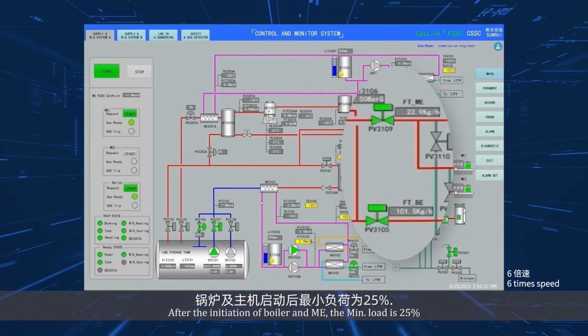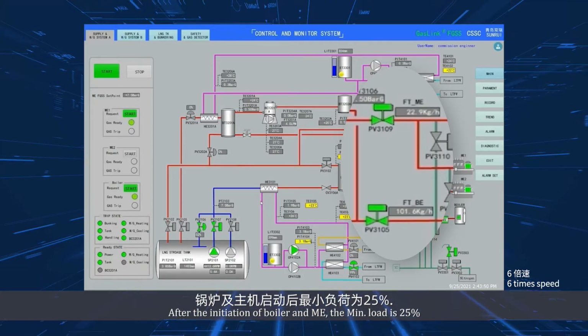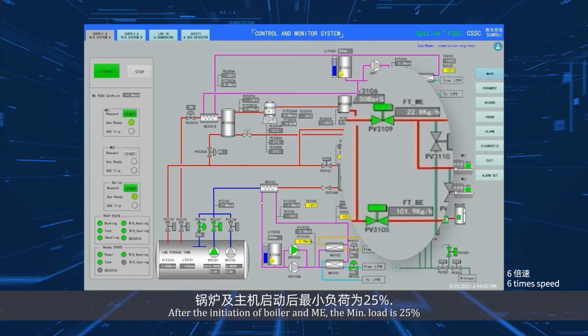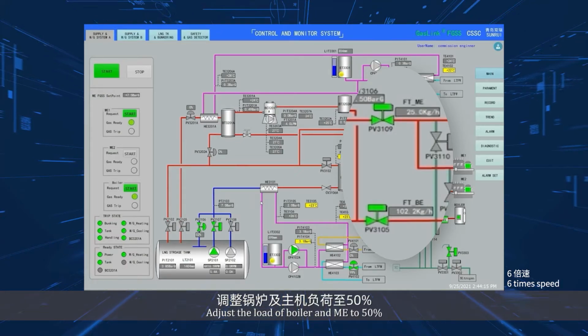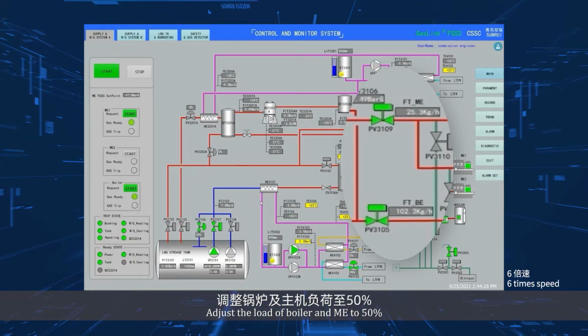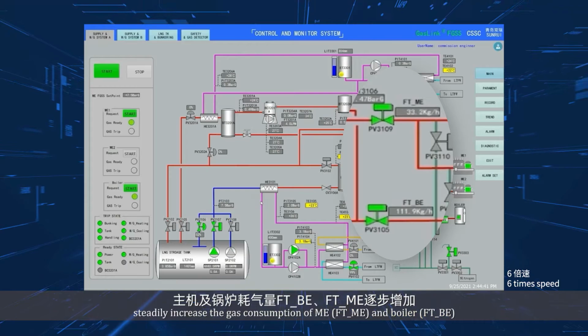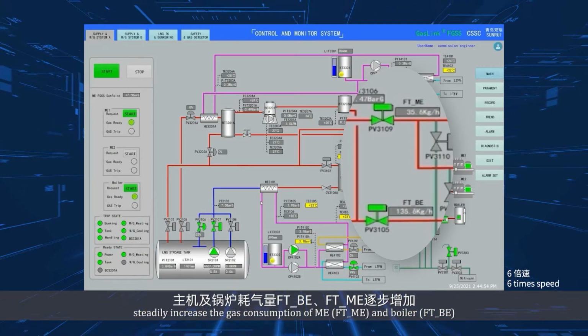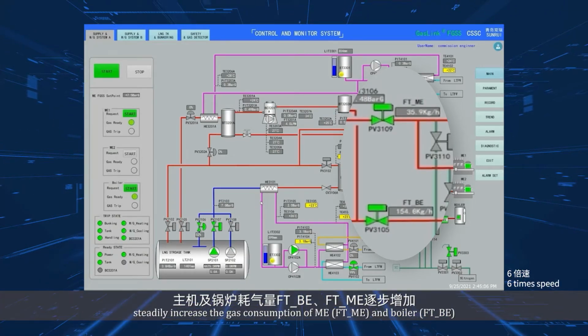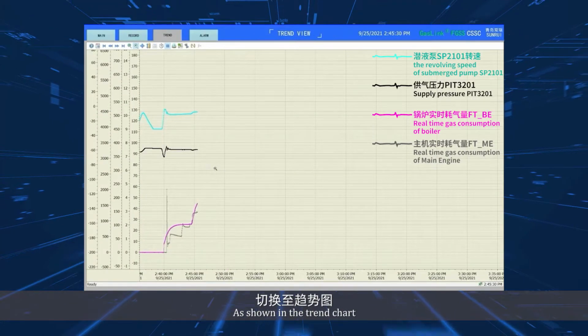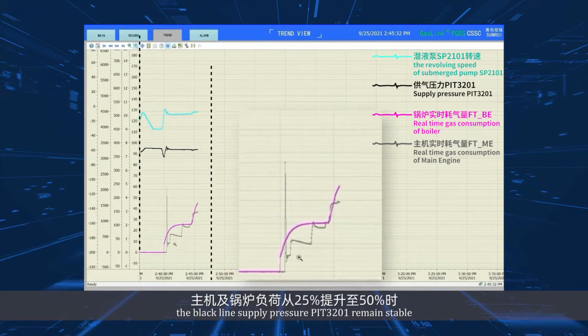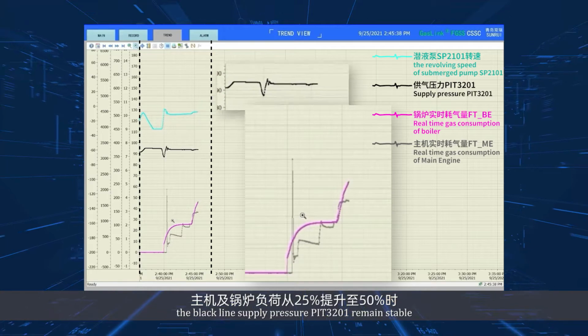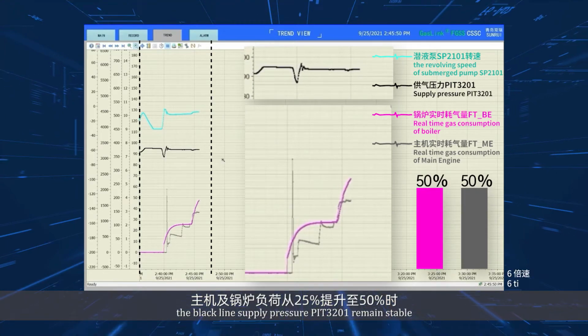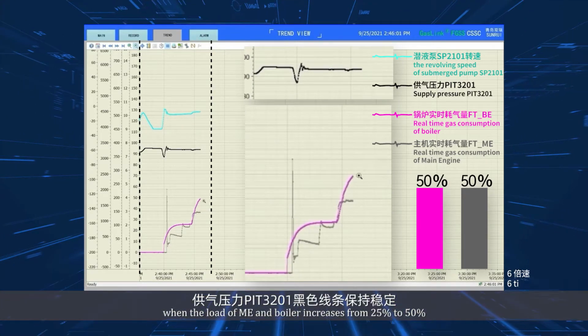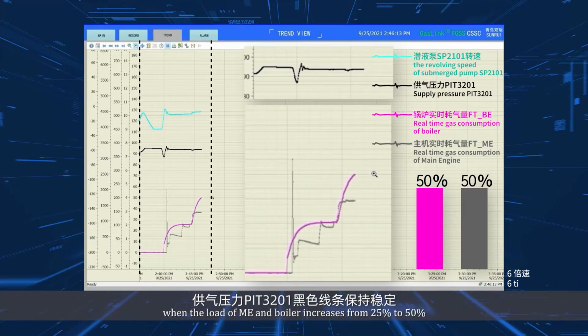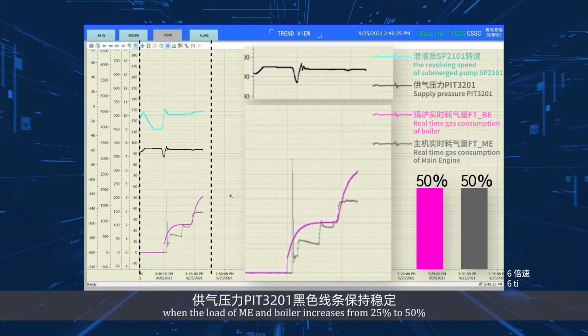After the initiation of boiler and ME, the minimum load is 25%. Adjust the load of boiler and ME to 50%. Steadily increase the gas consumption of ME, FTME, and boiler, FTBE. As shown in the trend chart, the black line supply pressure PIT3201 remains stable when the load of ME and boiler increases from 25% to 50%.